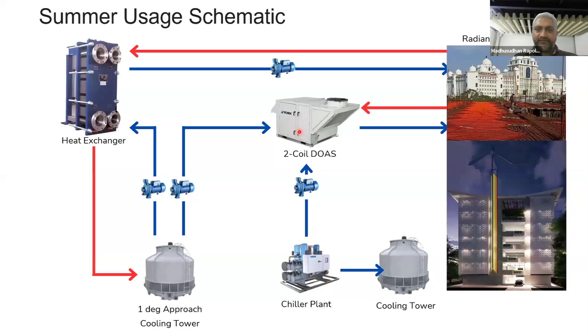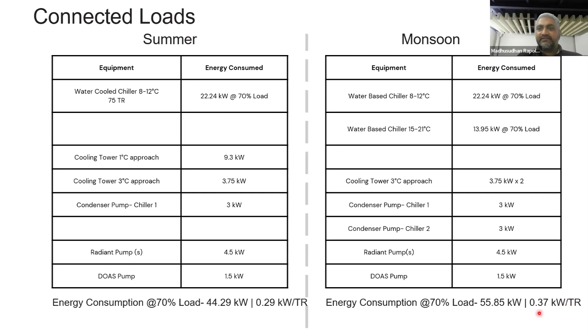So there are two different operating modes. One for summer, where the cooling tower is used, and we call it structure cooling instead of radiant cooling. You will see that the energy consumption is very low, close to about 0.3 kilowatt per ton. In monsoon, since we would end up using the chiller, the connected load would be around 0.37 kilowatt per ton. Those who are aware of energy being consumed by a centralized air conditioning system will understand that these are very, very efficient systems. And if you design things this way, then the path to net zero buildings becomes much shorter.